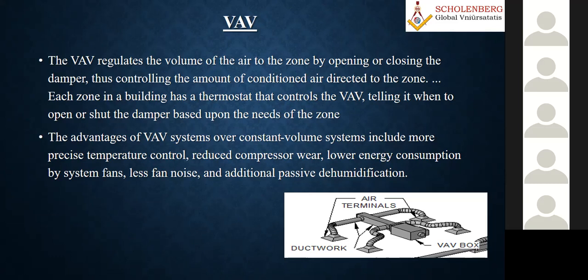In the constant air volume system, during the commissioning time, they set the set point of the damper. Even if you want to adjust the damper, there are mechanical linkages, nothing automatic. Many times during air balancing, they put a mark and also put a sticker saying don't change the settings, which you can see in old places. Because sometimes maintenance people come, and these variable control dampers are there. If they adjust them, the entire air balancing done during testing and commissioning may collapse, and doing the balancing and testing again will definitely be a difficult task. Majority of the time the maintenance people create problems, and some people will have more cooling while some will have starvation. So that is how the VAV system has an added advantage.